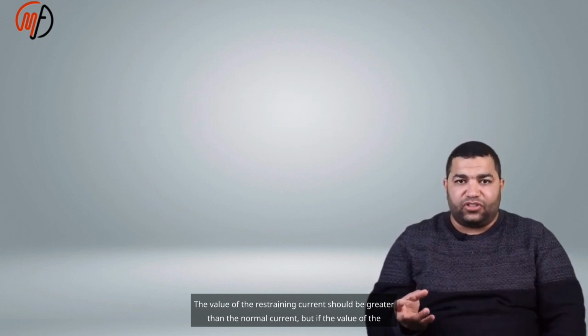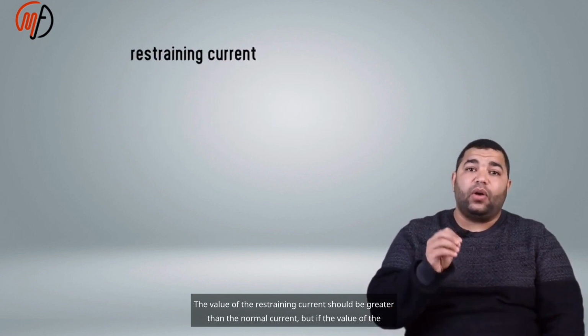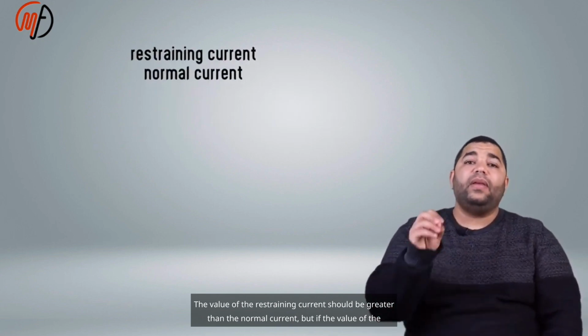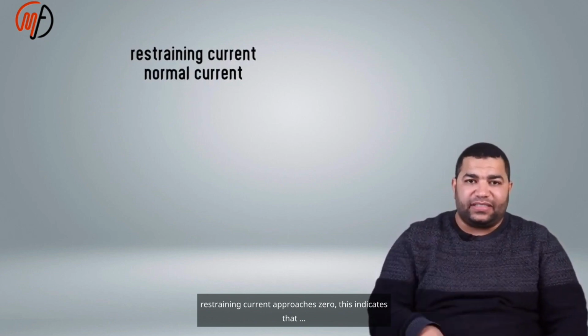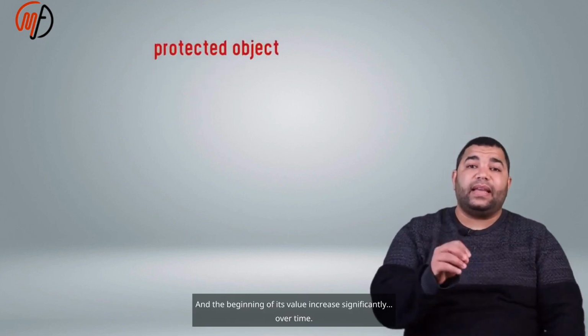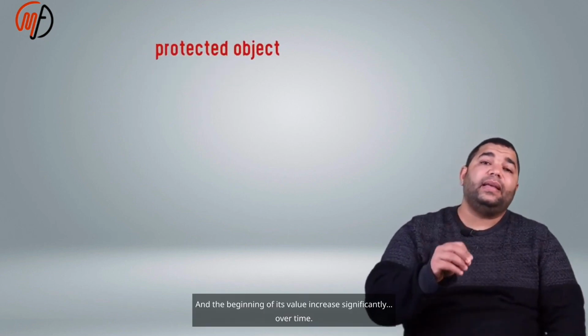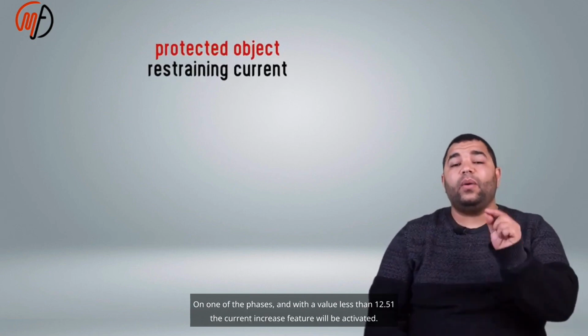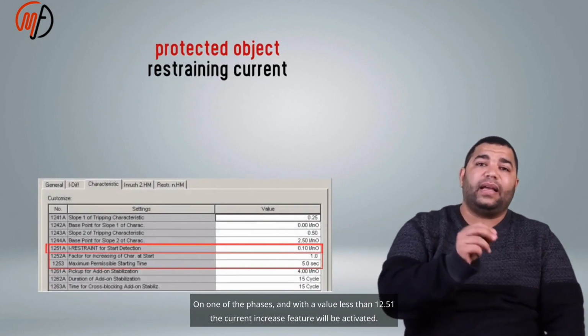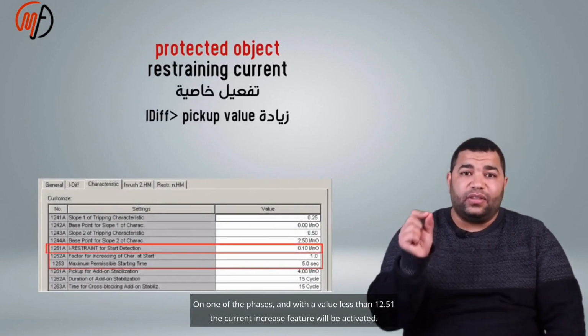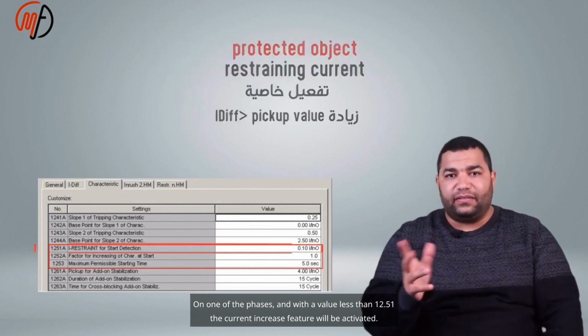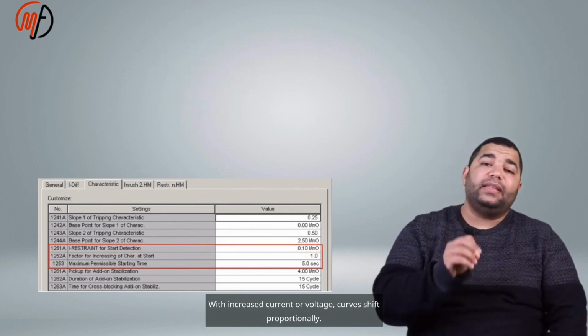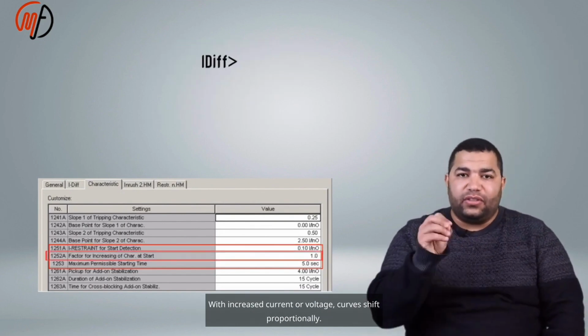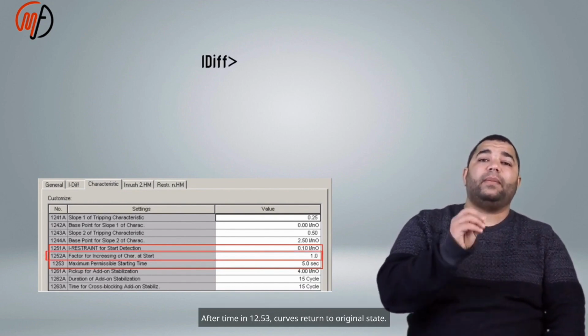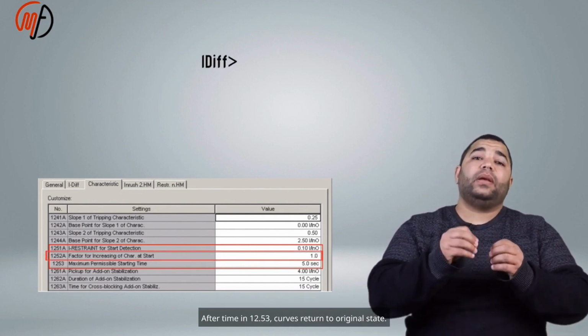The value of the restraining current should be greater than the normal current. But if the value of the restraining current approaches zero, the value increases significantly over time. On one of the phases, with a value less than 1251, the current increase feature will be activated. The factor in 1252 increases it. With increased current or voltage, the curves shift proportionally. After the time in 1253, the curves return to their original state.